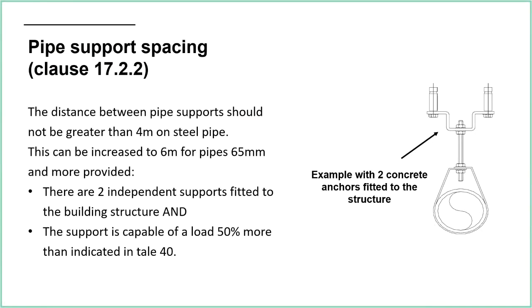So we're using 2 concrete anchors, and each concrete anchor is capable of the load plus 50%. Or maybe the whole bracket is 150% of the total in Table 40. But yeah, you get the idea. We're just like our water supplies, superior water supplies, duplicate water supplies, building in redundancy. It's a bit like this with this bracket. We have multiple fixing points, and then it's extra secure, which means that we can relax some of the other requirements, such as going from 4 meters to 6 meters maximum.